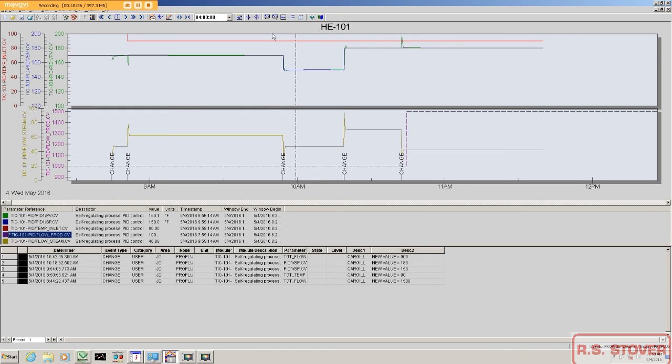So we hit that. We get a dotted line here to signify that this is on a different time scale than the rest of it. Let's take a look at our timestamp. Everything else is at 9:59, but our product flow is at 7:59. And we can keep going back. We can go forward. Unlike the scroll buttons, both the trend forward and trend back are equal to half of the time span, so it doesn't matter there.